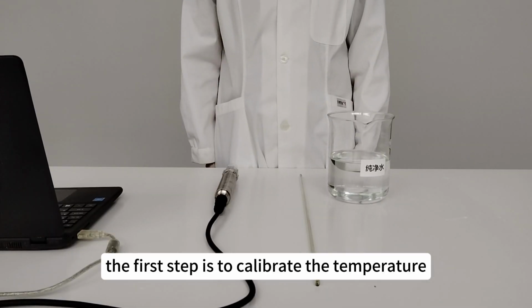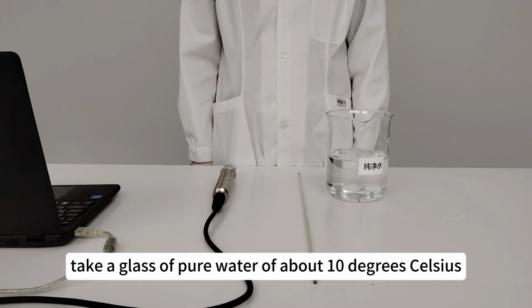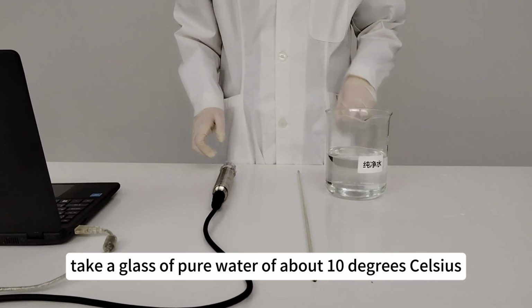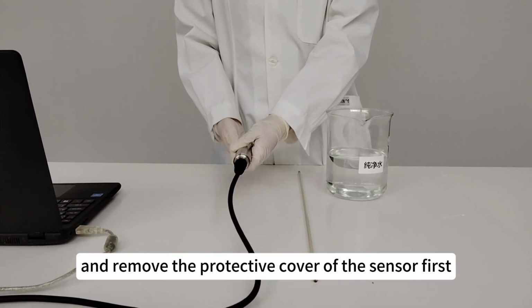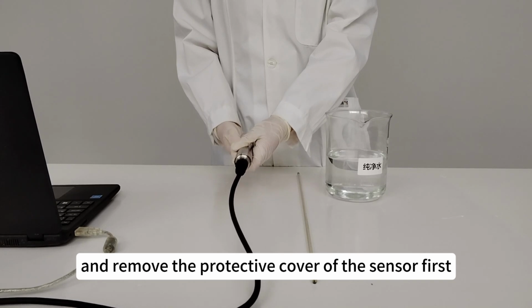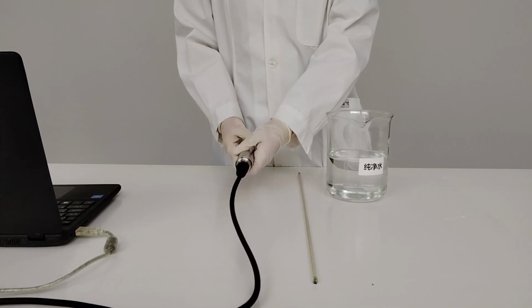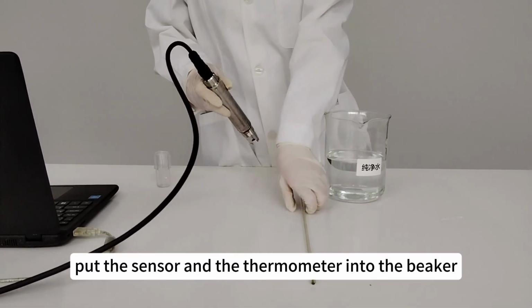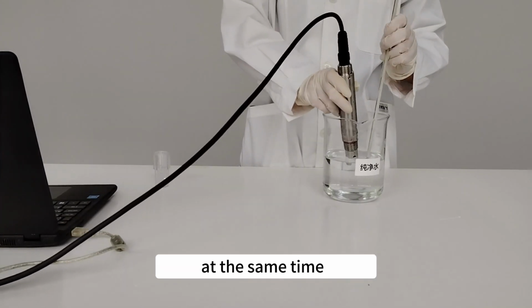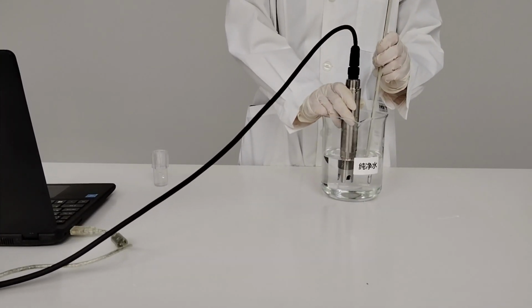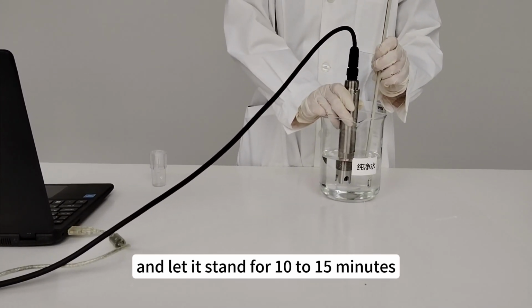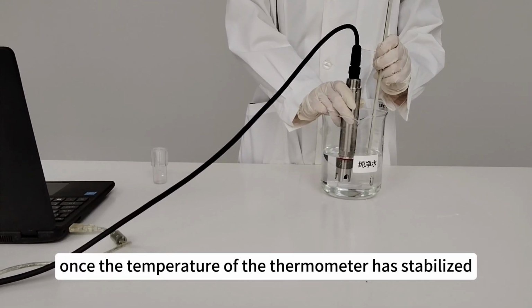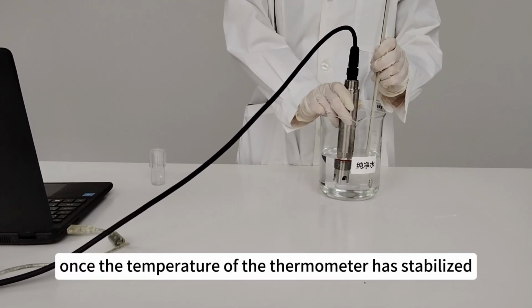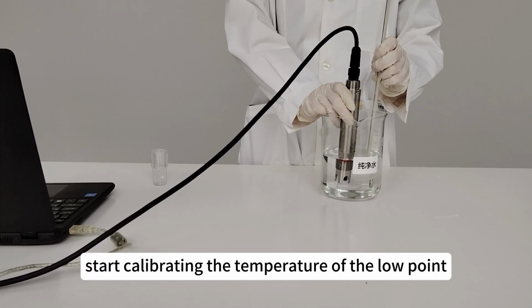The first step is to calibrate the temperature. Take a glass of pure water of about 10 degrees Celsius and remove the protective cover of the sensor first. Then put the sensor and the thermometer into the beaker at the same time and let it stand for 10 to 15 minutes. Once the temperature of the thermometer has stabilized, start calibrating the temperature of the low point.